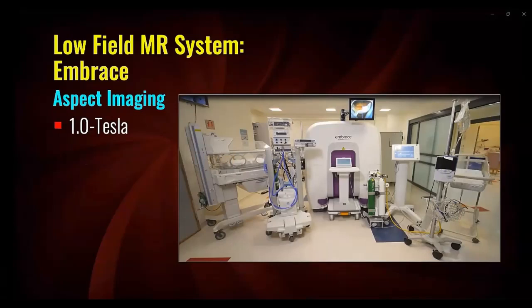The Embrace MR system is self-shielded and does not require special siting considerations. Because of its unique design, there are no issues related to ferromagnetic objects or the need for MR-conditional patient support equipment. By way of example, take a look at the Embrace scanner installation in a typical neonatal ICU.